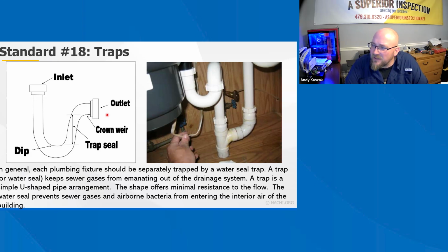The vertical distance from the fixture outlet to the trap weir should not be greater than 24 inches. The limitation of the vertical distance is designed to control the velocity of the drainage flow. If the trap is located too far from the fixture, the trap may self-siphon the water out of the trap. The horizontal distance from the fixture outlet to the trap weir should not be greater than 30 inches, measured from the center line of the fixture outlet to the center line of the inlet trap. It is desirable to locate the trap as close as possible to the fixture to avoid the need for a long drain pipe on the inlet side of the trap to be installed. There will not be enough flow energy to move waste if the horizontal distance exceeds this limit.